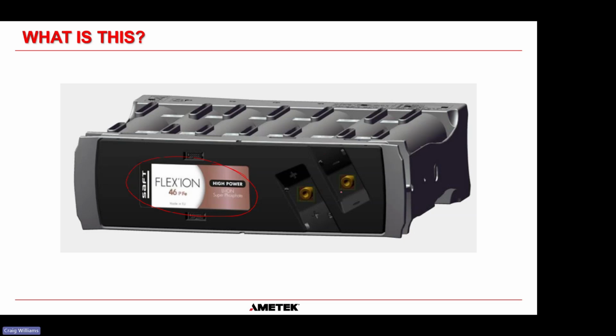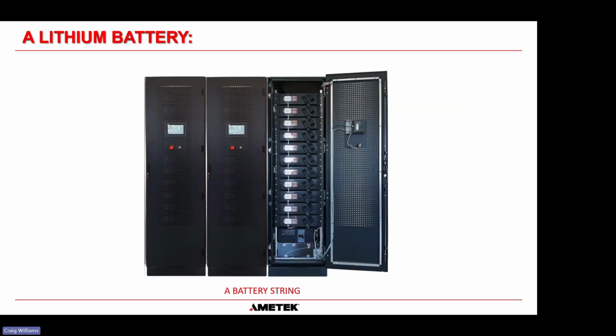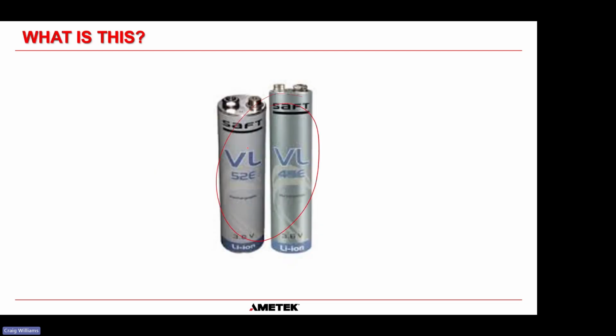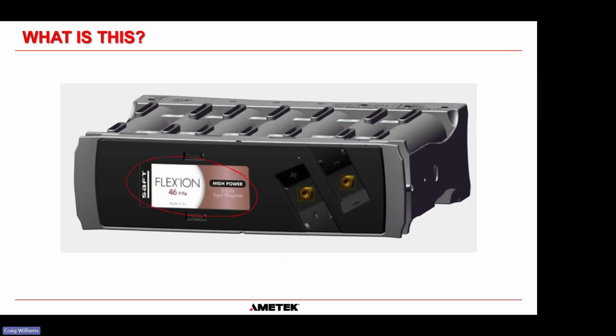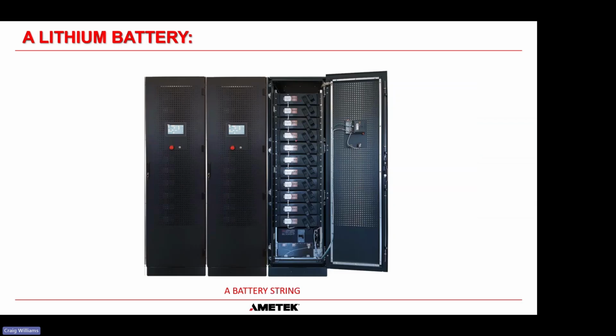So inside here, you will see that there are numerous cells that look like this connected in series and parallel to give the rating that they need. So this is called a module, and here is the main positive, and this is the main negative. And then what they do is they put the modules in series to get the correct battery string that they need inside a cabinet. So this is classed as a lithium battery string. Okay, so we had the lithium cell, then we had the lithium module, and now we have a lithium battery string.